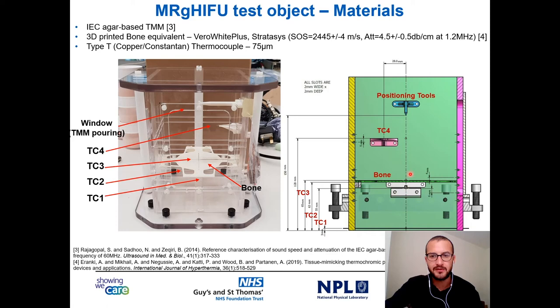When you want to build the phantom, the first problem you have is the choice of materials. Materials must be compatible with the technology of interest, which in this case are ultrasound and magnetic resonance imaging. We use the well-known IEC recipe, which is an agar-based tissue-mimicking material with speed of sound 1540 m/s and attenuation 0.5 dB per centimeter. We use a 3D-printed bone equivalent disc to mimic flat bone, and type T copper-constantan thermocouples of size 75 micron, to be MRI compatible and to minimize interaction with ultrasound fields. Thermocouples were placed in the region below and above the bone, and one thermocouple was used as reference. Positioning tools and engravings were manufactured to support thermocouple identification in 3D space in MRI.